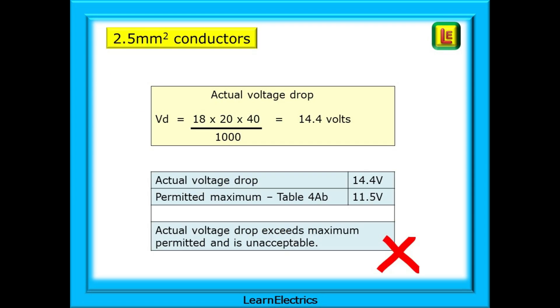For an acceptable circuit the volts drop will be equal to or less than that. This is the calculation for 2.5 square millimetre conductors. We are only interested in the line and neutral as we are assuming a fault free circuit. And 40 metres is the length just one way, not measured there and back. The actual voltage drop is 14.4 volts and is greater than the permitted 11.5 volts.